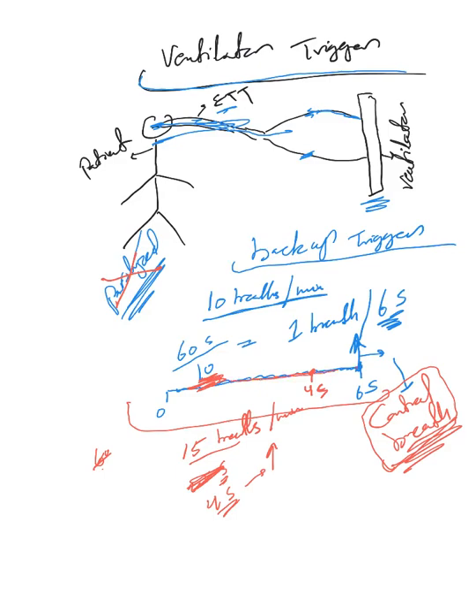What happens? The ventilator, every time there is a breath initiated before the 6 seconds, will reset back to zero, listening again for 6 seconds. So if the patient here is breathing 15 breaths on his own, all the breaths will be patient-triggered, all the breaths will be assist breaths, and he will have zero control breaths because he always initiated breath before the 6 second interval.